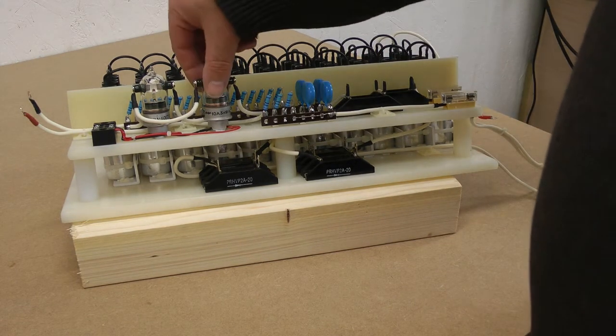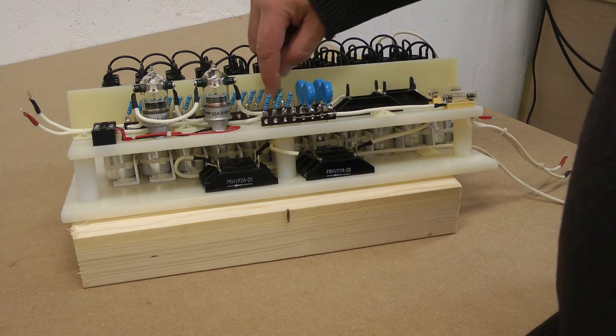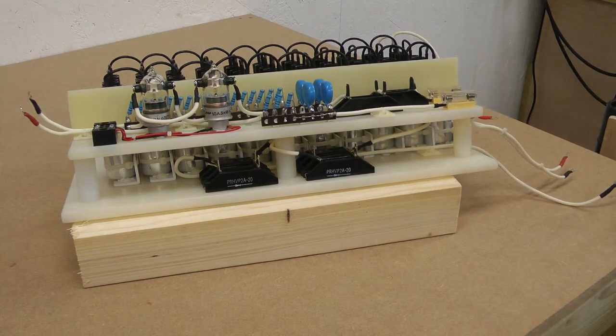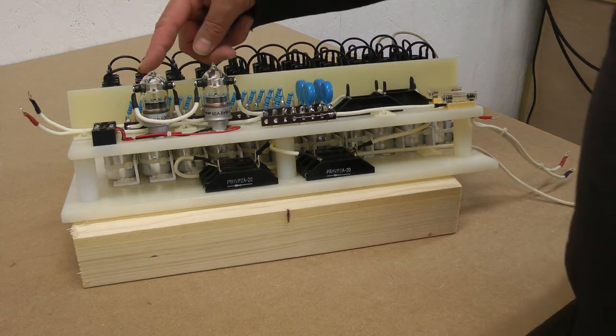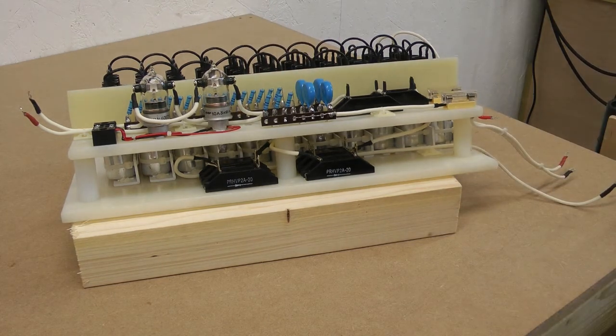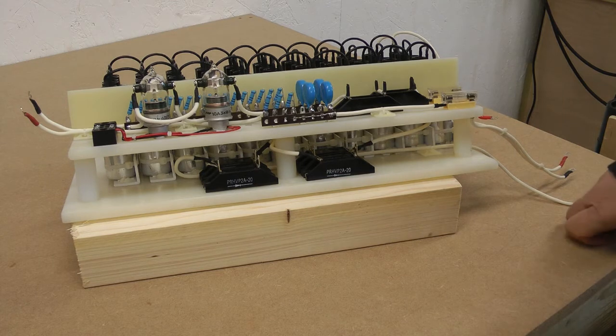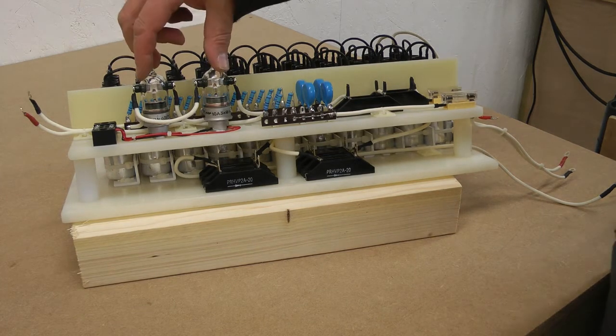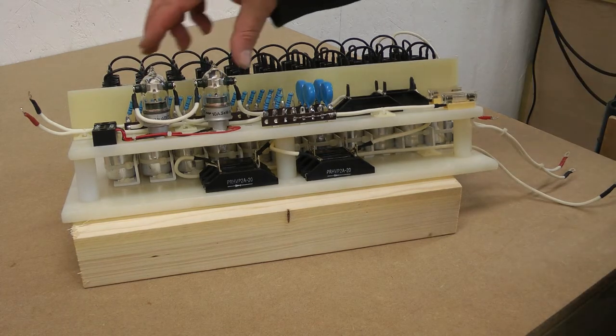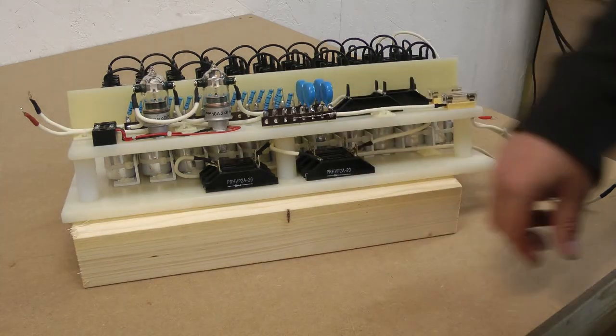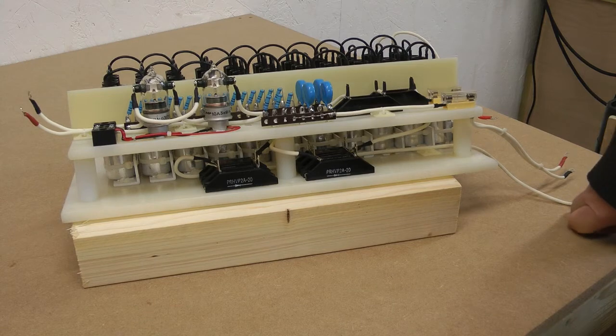For 5 kilovolts, this comes on and it takes a tap out of the second one here with a return. That gives us 5 1 megohm resistors. So we take 5 kilovolts down to 1 milliamp. And this one here, this vacuum relay, is off the tap for 10 resistors. So that then gives us 10 kilovolts with 10 resistors down to 1 milliamp again. So the switch at the front between 5, 10 and 20 kilovolts actually controls the low voltage side switching of these relays, where with no power, both relays off, the meter would be in 20 kilovolt as the default mode. And that works reliably and safely.